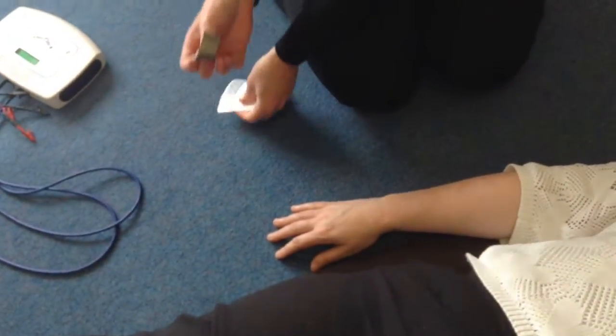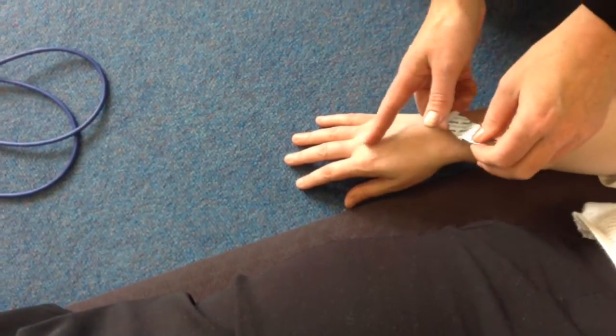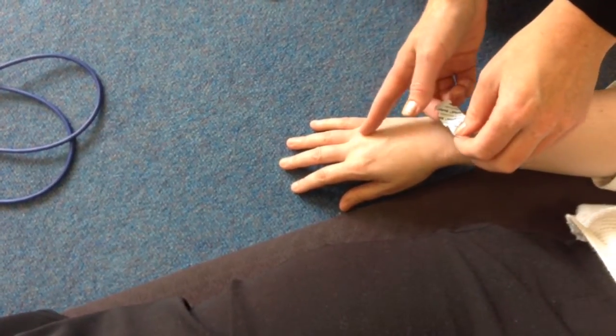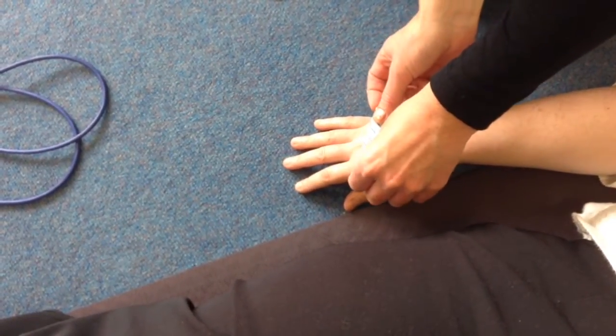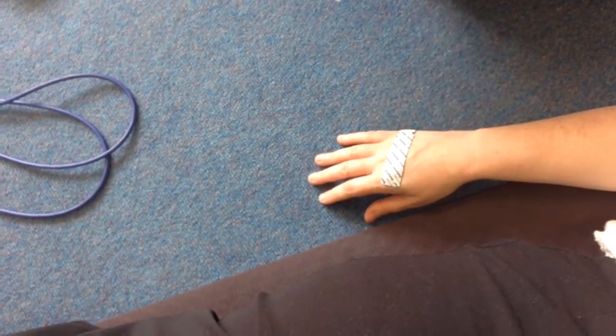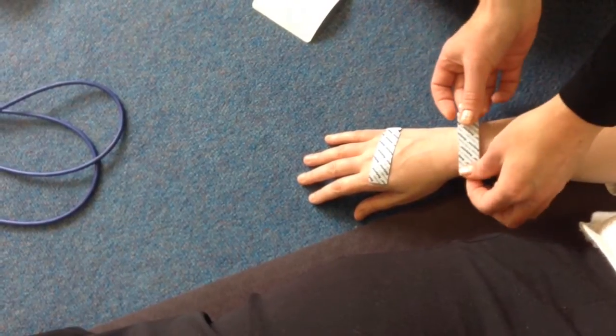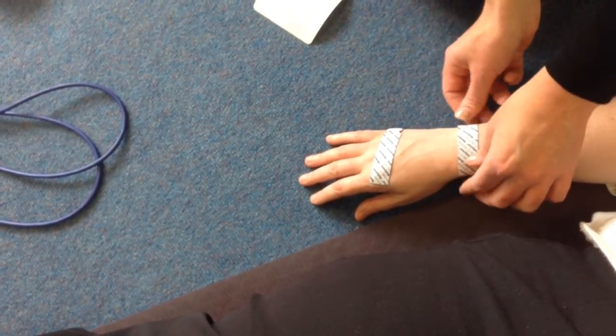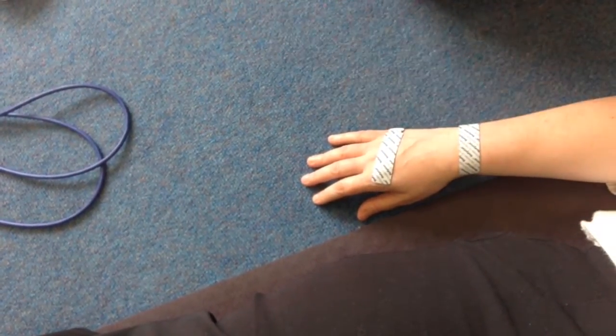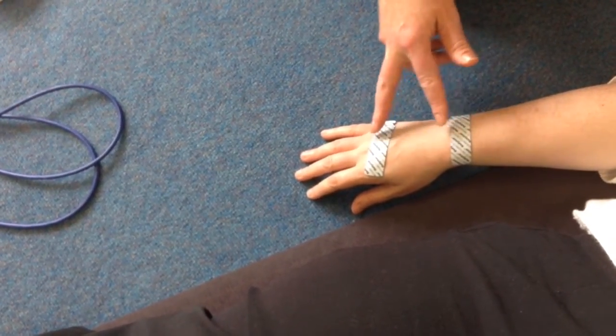Then positioning the electrodes on the hand, we follow the same rules. Just follow the knuckle bones along the hand and position the electrodes just underneath them, and again just in between the wrist bones here. It will overlap a little bit, and again the distance between the two must be at least three to five centimeters.